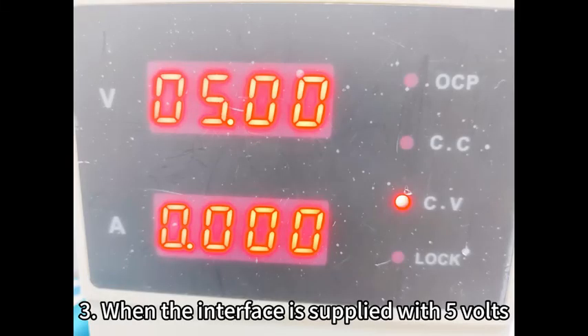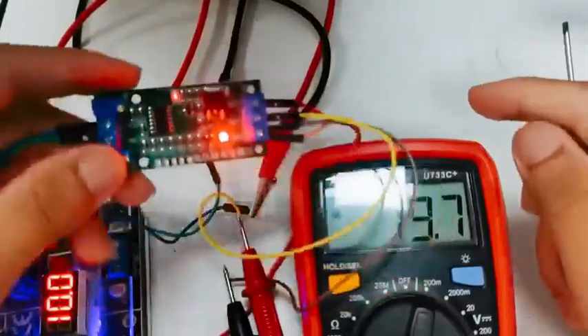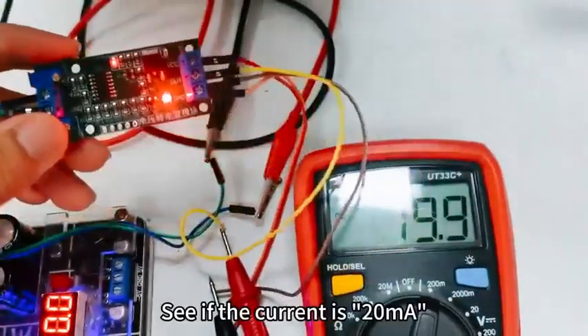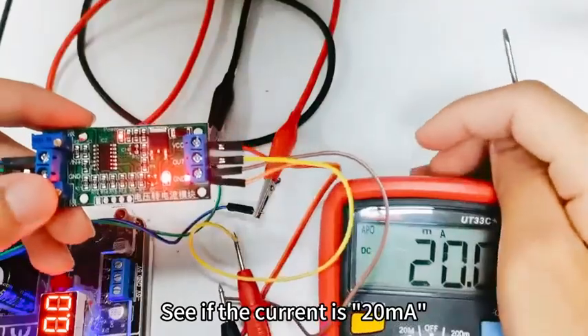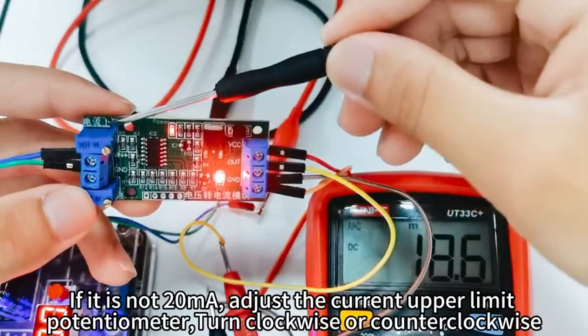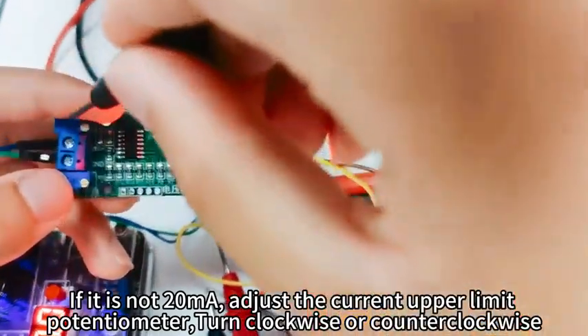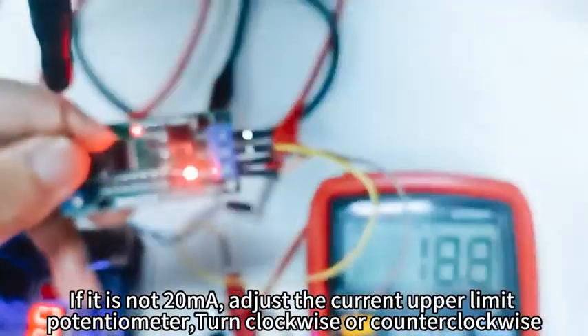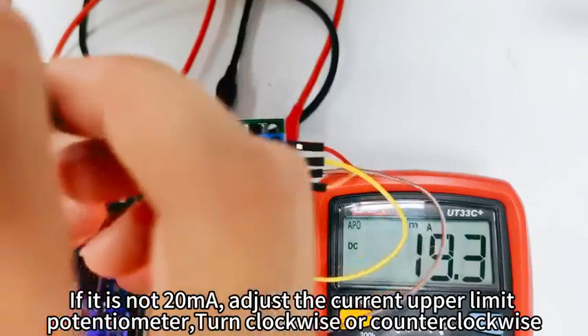Step 3: When the interface is supplied with 5V, see if the current is 20mA. If it is not 20mA, adjust the current upper limit potentiometer, turn clockwise or counterclockwise.